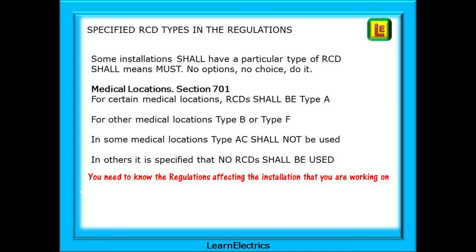The regulations also tell us that some installations shall have a particular type of RCD. 'Shall' means must — no options, no choice, do it. For example, in certain medical locations the RCD shall be type A — no choice. For other medical locations it is a type B or type F. In some other parts of a medical location, type AC RCDs shall not be used — they are not allowed — and even in others it is specified that no RCDs shall be used at all. So you could have different RCD requirements in different parts of just one building.